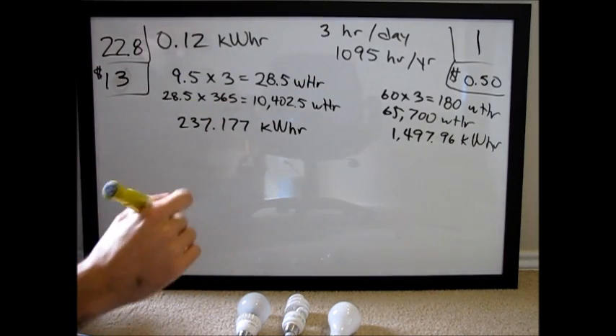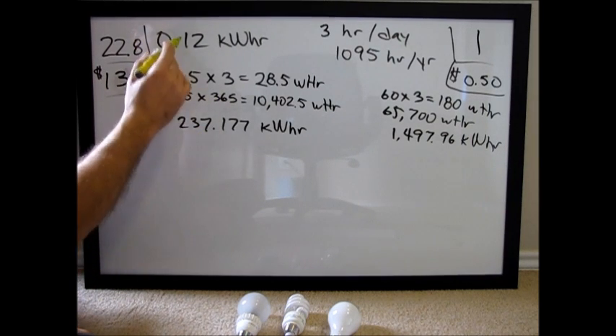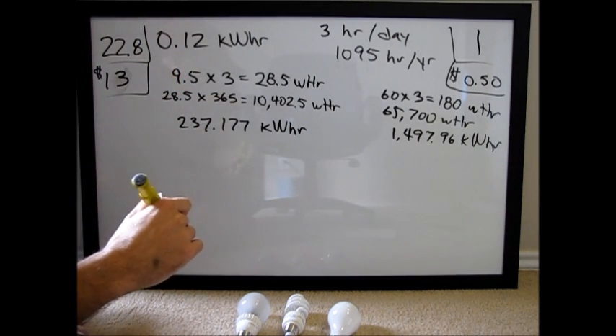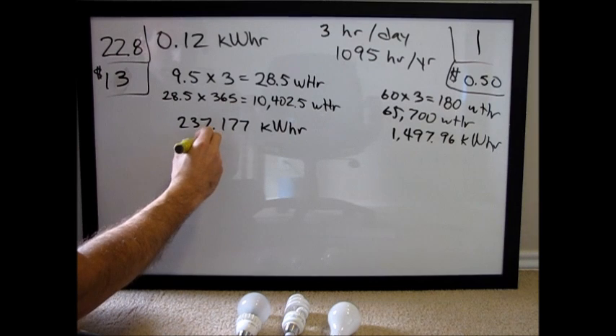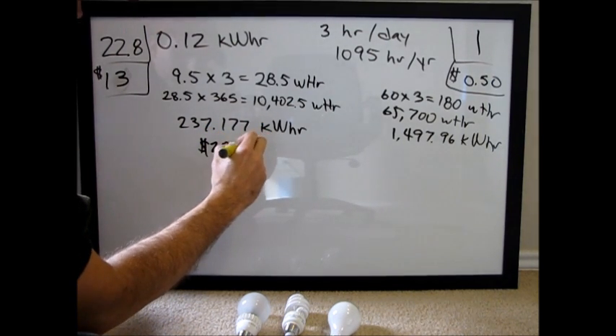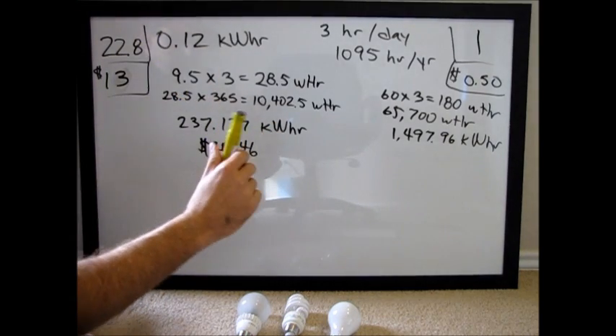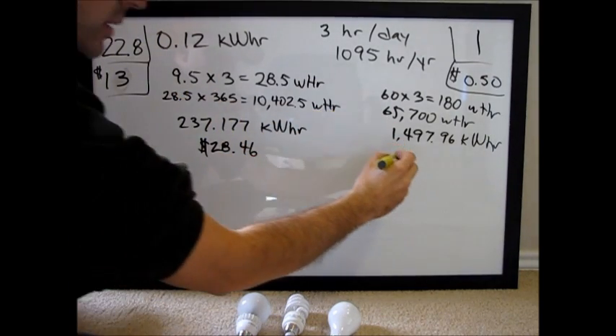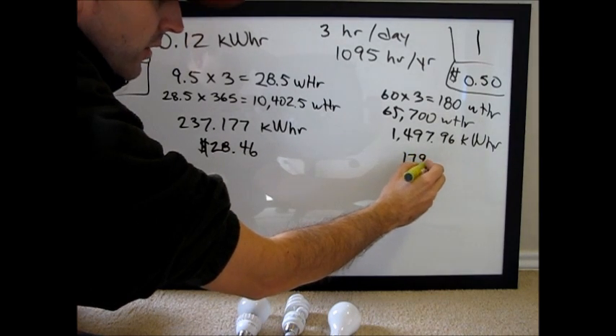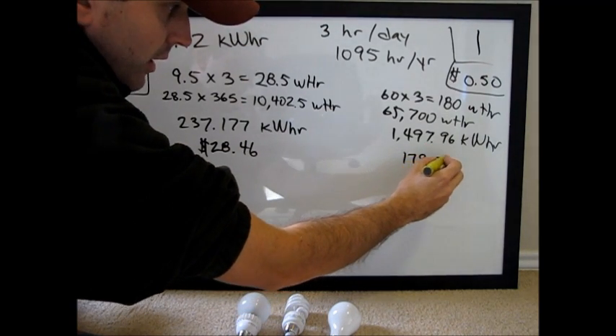And now, to finish the comparison, we need to figure out the cost of the electricity. So we multiply both of these by 0.12. This one ends up being $28.46 for the 22.8 years. This one ends up being $179.76.